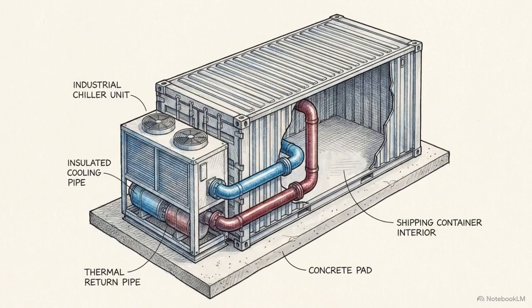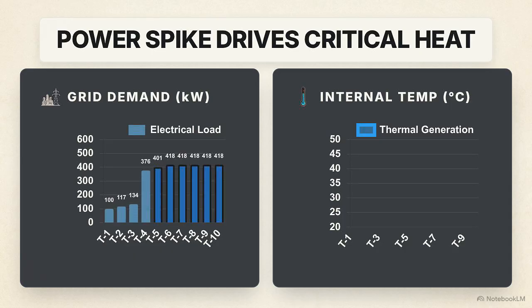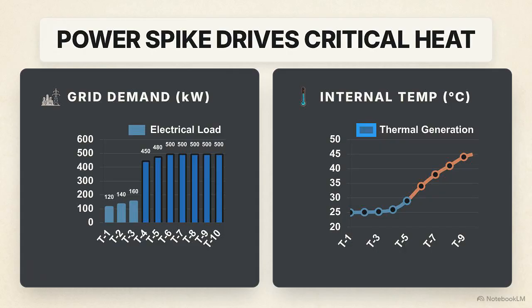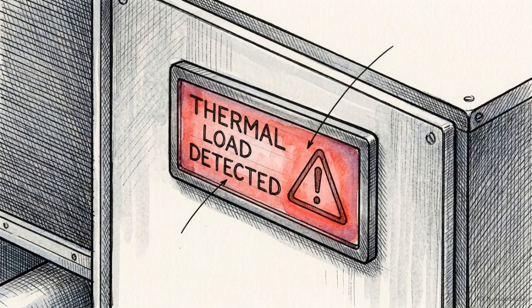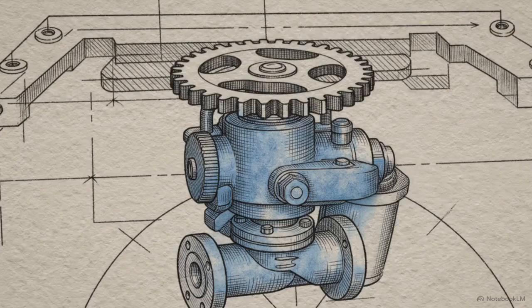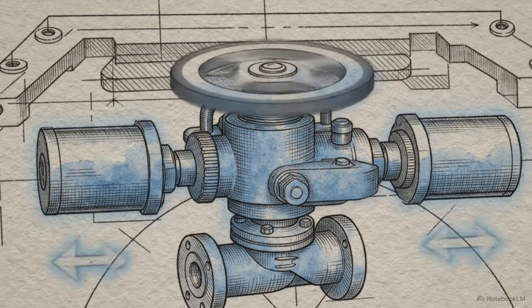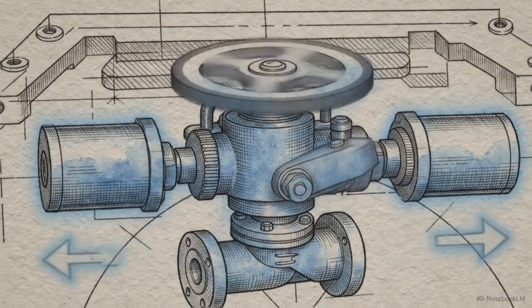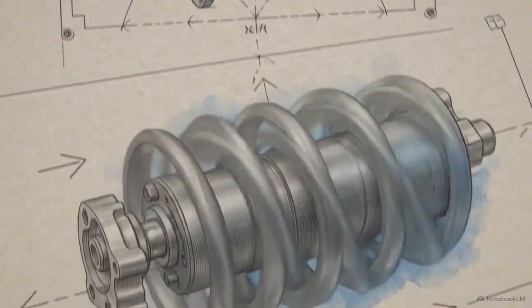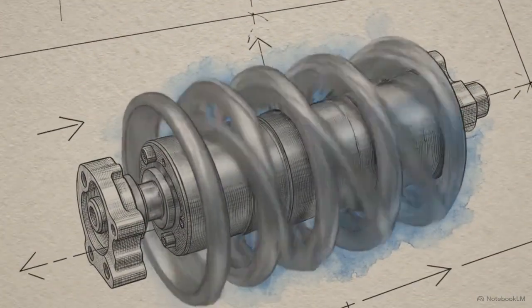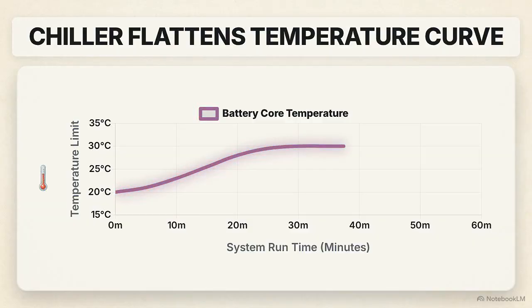When we zoom out, we see the fully assembled dual-loop chiller unit integrated seamlessly into the 500-kilowatt battery container. The true test of this design occurs during a sudden grid power spike, when the utility demands maximum output and the internal battery temperatures climb steeply. The system responds with a rapid, orchestrated cascade. The sensors detect the thermal load, the electronic expansion valve opens wider to allow more refrigerant, the scroll compressor ramps up its RPMs, and the battery temperature curve is aggressively flattened.